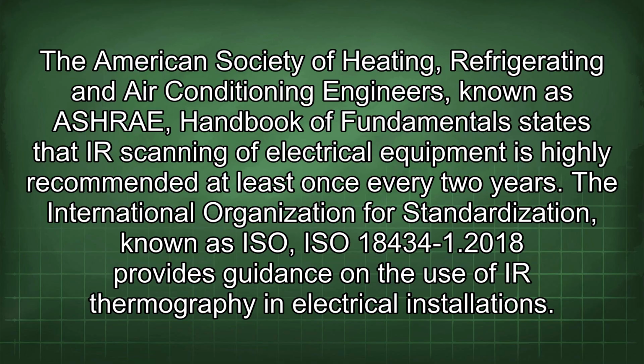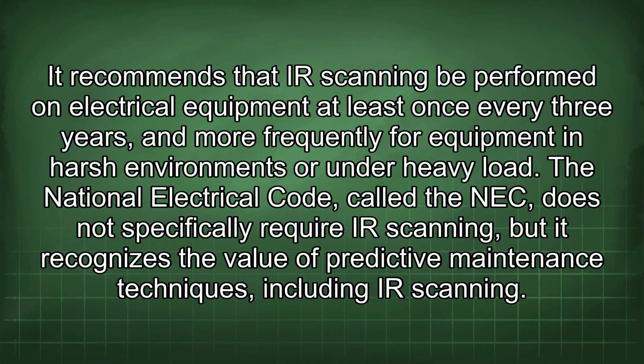The International Organization for Standardization, known as ISO, ISO 18434-1:2008, provides guidance on the use of IR thermography in electrical installations. It recommends that IR scanning be performed on electrical equipment at least once every 3 years, and more frequently for equipment in harsh environments or under heavy load.